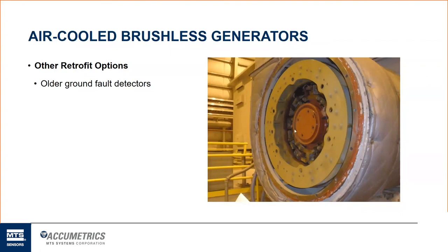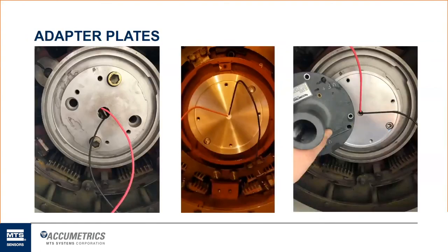Then this red piece is what's called the rotor end cap. So this is all what would normally be on a smaller air-cooled unit. This is very typical to what we would see. So we came up with the concept of, why can't we just mount our transmitter right to the end of the shaft and just have them modify this rotor end cap by putting a small hole in the center of the end cap. And so that's the style that we do for many of our end of shaft systems. So here's an example of the rotor end cap that's been machined and modified with a hole in the center.